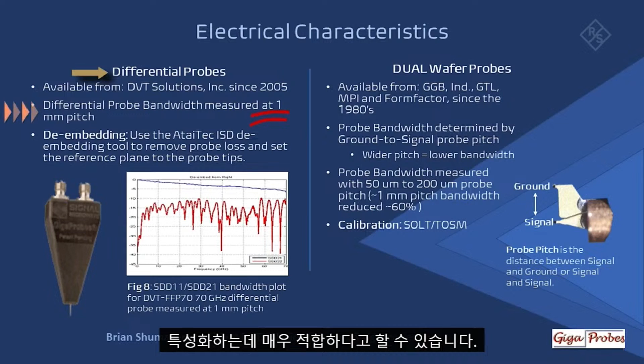A differential probe is ideal for characterizing differential traces on a printed circuit board. Differential probes are used to make time and frequency domain measurements of the final prototype printed circuit board product form against design specifications using visual analysis. The DVT FFP70 70 GHz probe could be used to characterize 56 GHz Nyquist S parameters for PAM4 220 gigabits encoding designs. Figure 9 illustrates using a VNA to probe a device test board and applying De-Embedding to reset the VNA measurement point to measure return loss on the transceiver outputs while the chip is active.